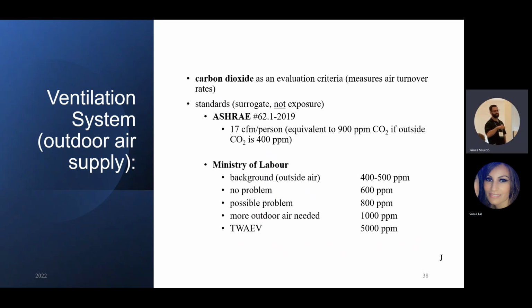So again, we're going to mention ASHRAE here, which is the American Society of Heating, Refrigeration, and Air Conditioning Engineers. What they like to use is carbon dioxide as an evaluation of the air turnover rates in the building. They do have some documentation that says approximately 17 cubic feet per minute per person should be coming into the building. And this is equivalent to about 900 parts per million of carbon dioxide, if the outdoor carbon dioxide is about 400. A lot of times we'll be asked how much air should be coming in, and it all comes down to how many people are in the occupied space.